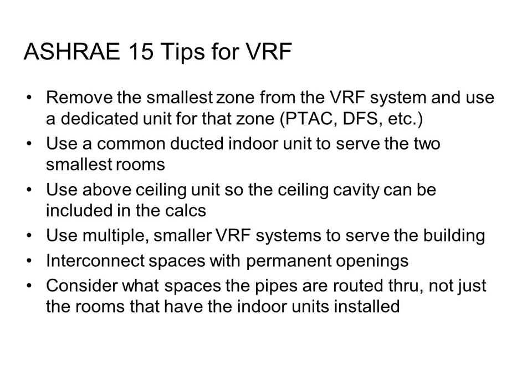So depending on whether I have 100 feet of pipe or I have 600 feet of pipe makes a huge difference in my volume. With that being said, it's usually fairly easy to get under the requirements if you're talking about small systems, 6, 8, 10 tons. When you go above that, it becomes more and more critical that you pay attention because you're probably going to be above the refrigeration volumes in some of your zones. But I can't give you a tonnage answer, Tyler, because it depends on how much pipe you're going to run.